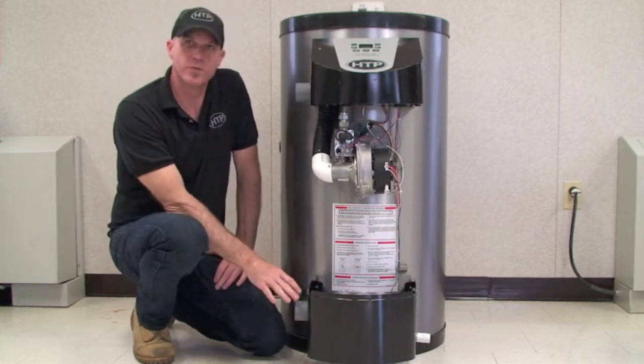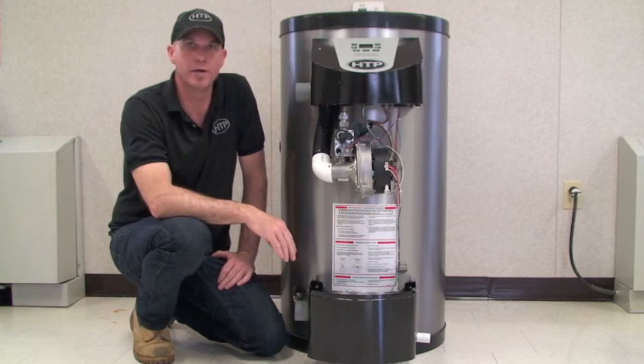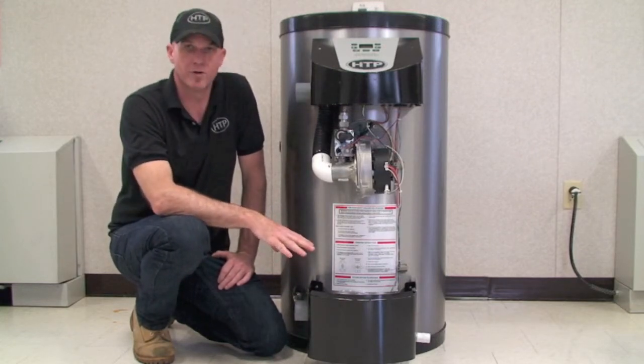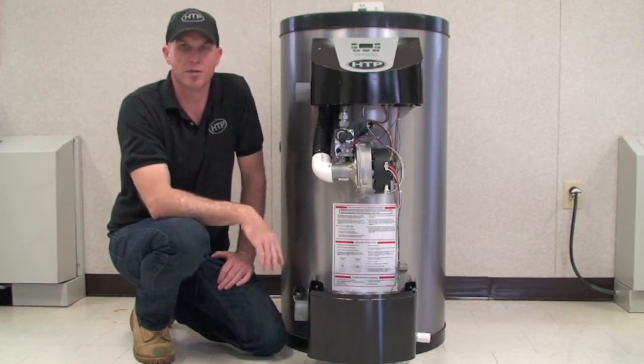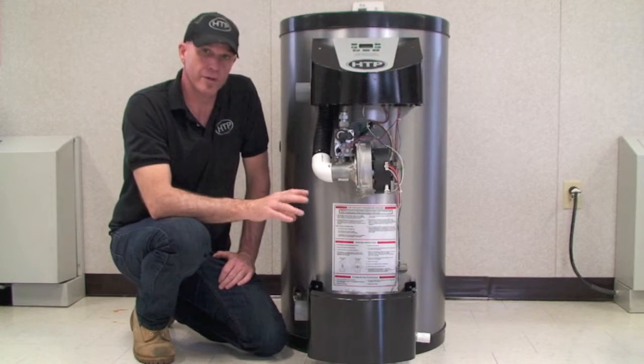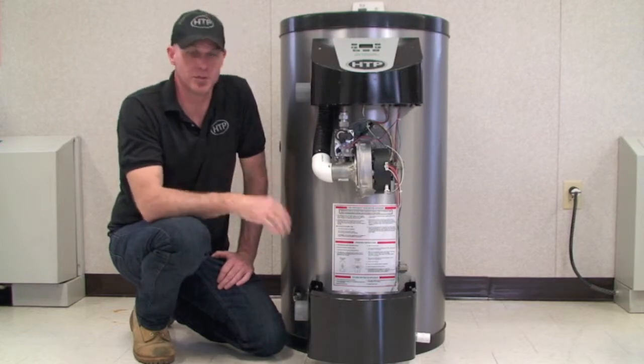The other option for this unit is to pump the condensate out. If we don't have a floor drain or a drain anywhere in the area, condensate pumps are available through HTP and local suppliers that can be put onto this unit and just pump the condensate out. It is also very important that the condensate pipe remains unobstructed and supported all the way down into the drain.